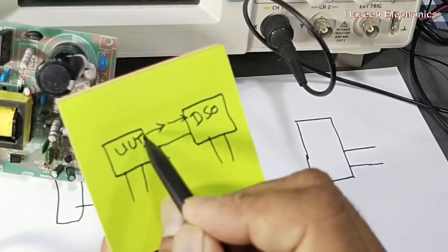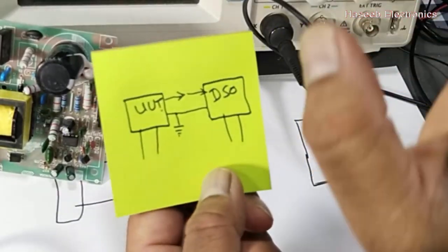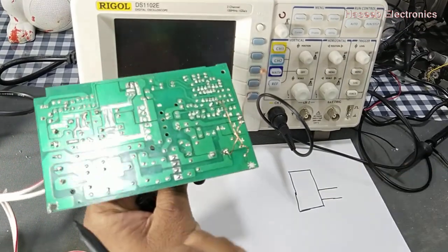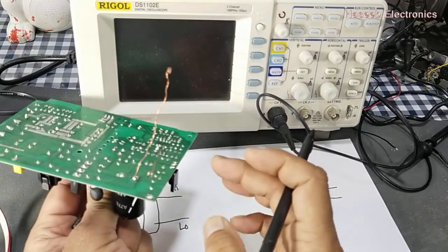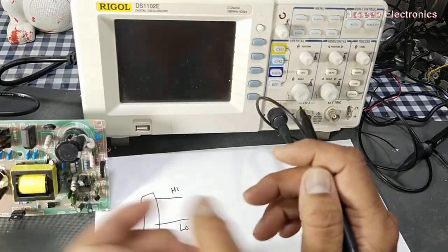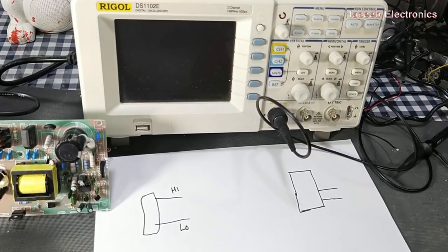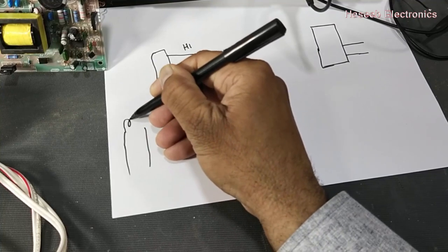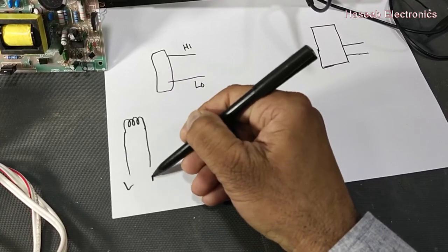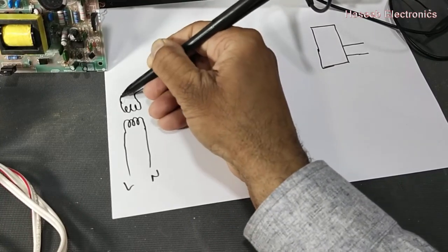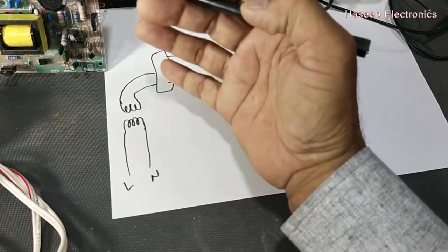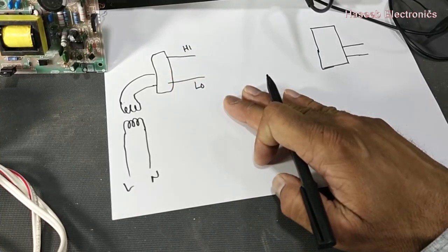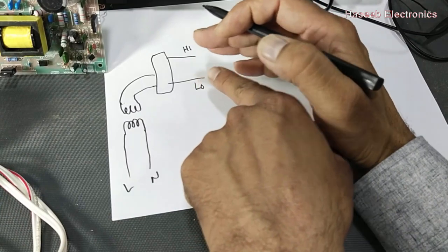What are the safety parameters? First, if we are working on an unisolated circuit supplied with direct line voltage, it's best practice to isolate our test bench. If our test bench does not have any isolation transformer, we should add one. This isolates line and neutral, making the unit under test isolated for human safety.